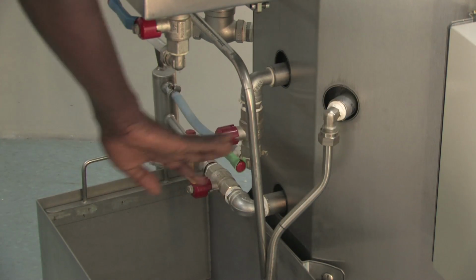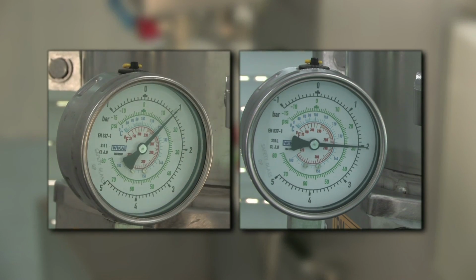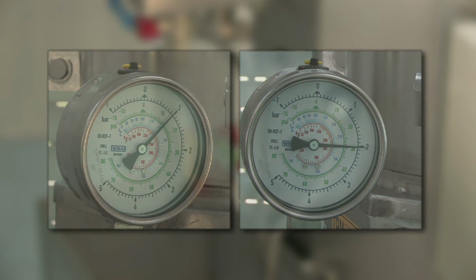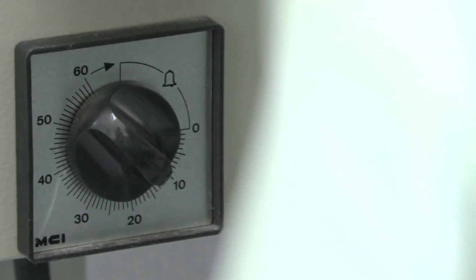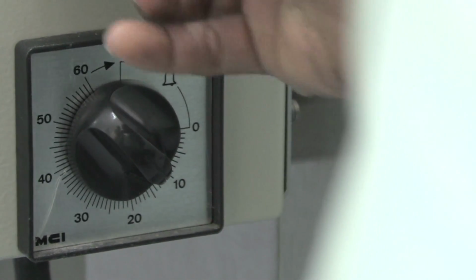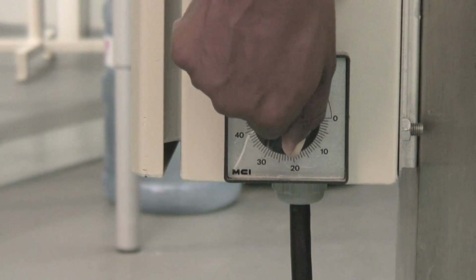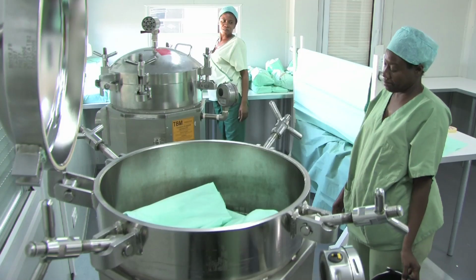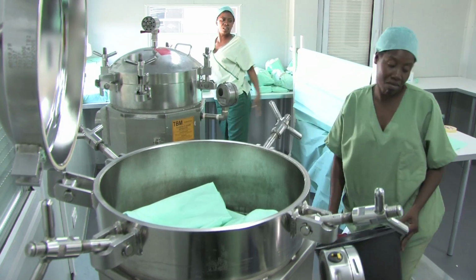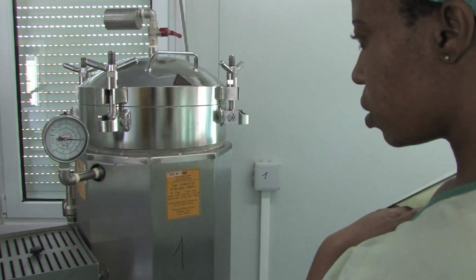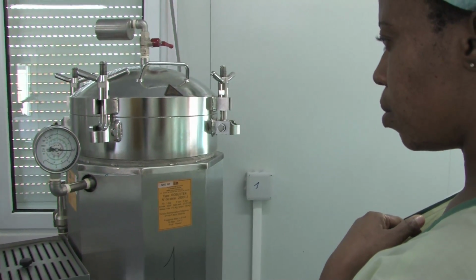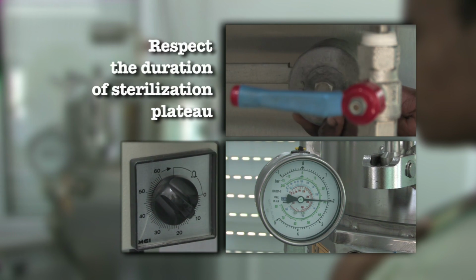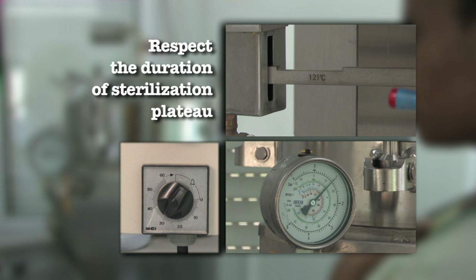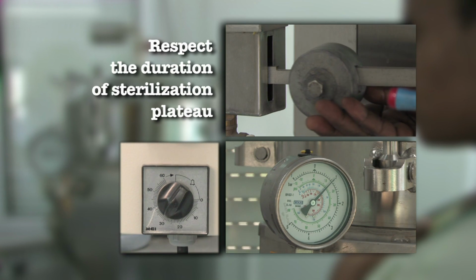4. After the 3rd purge, reclose the green valve and let the pressure rise to the pressure needed for the desired sterilization plateau. When the pressure reaches either 1 bar or 2 bars, depending on the cycle chosen, set the timer for 10 or 30 minutes. It will signal the end of the sterilization plateau. A sterilization cycle is considered valid when all 3 parameters, steam temperature, steam pressure, and plateau duration, are achieved at the same time. That is 10 minutes at 134 degrees Celsius and 2 bars, or 30 minutes at 121 degrees Celsius and 1 bar.